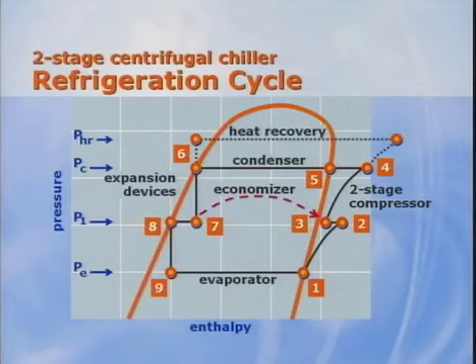Just like positive displacement compressors, power consumption is increased due to the higher pressures associated with heat recovery. However, the differences in the pressure enthalpy chart between a positive displacement compressor and a centrifugal compressor are not important when heat recovery is concerned, but the physical differences in the compressors themselves are. The first key point to keep in mind is that there is no physical component that forces refrigerant through a centrifugal compressor. The refrigerant flowing through the compressor is its own driver and its own inhibitor to prevent refrigerant from flowing in the wrong direction.